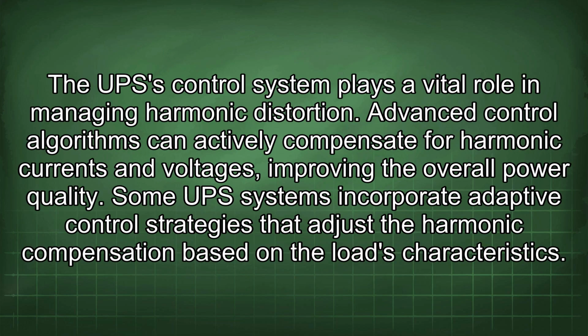The UPS control system plays a vital role in managing harmonic distortion. Advanced control algorithms can actively compensate for harmonic currents and voltages, improving the overall power quality. Some UPS systems incorporate adaptive control strategies that adjust the harmonic compensation based on the load's characteristics.